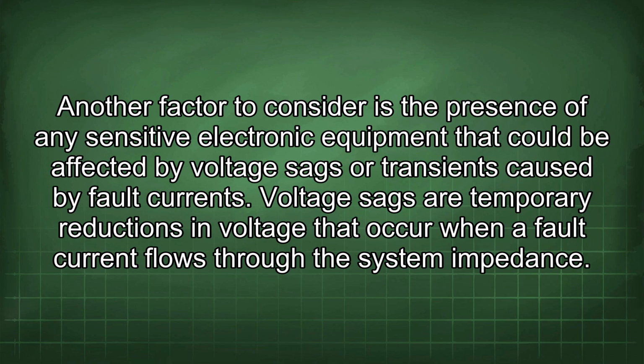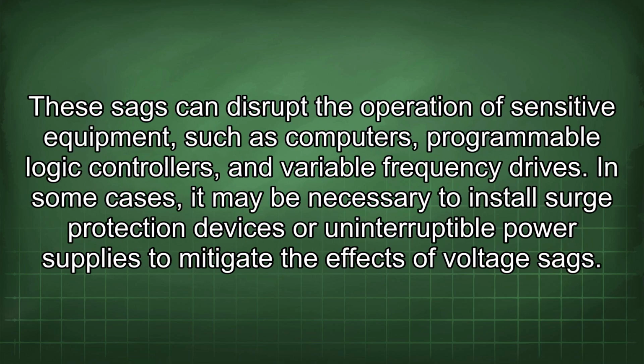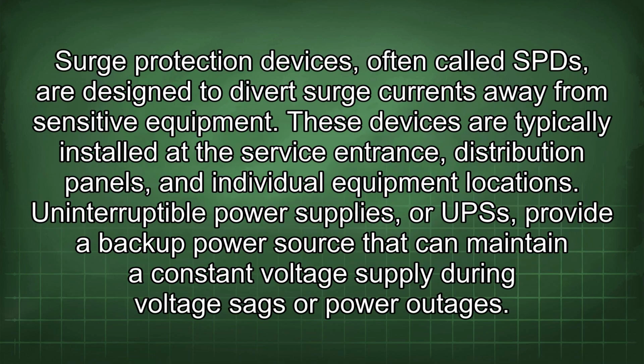Voltage sags are temporary reductions in voltage that occur when a fault current flows through the system impedance. These sags can disrupt the operation of sensitive equipment such as computers, programmable logic controllers, and variable frequency drives. In some cases, it may be necessary to install surge protection devices or uninterruptible power supplies to mitigate the effects of voltage sags. Surge protection devices, often called SPDs, are designed to divert surge currents away from sensitive equipment.